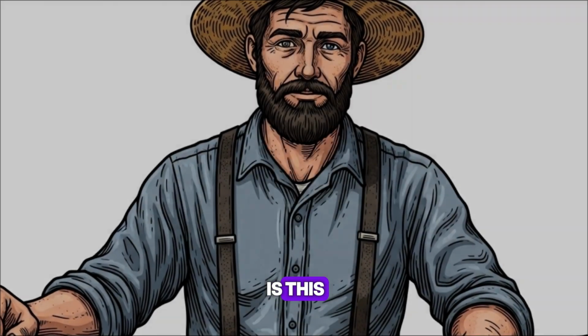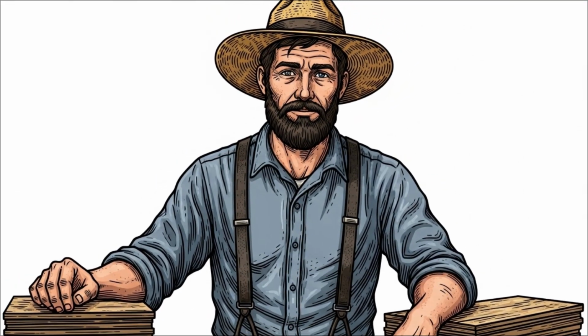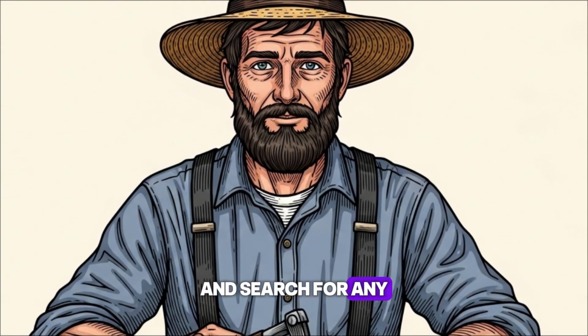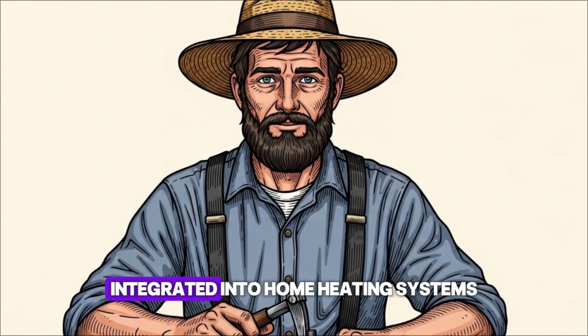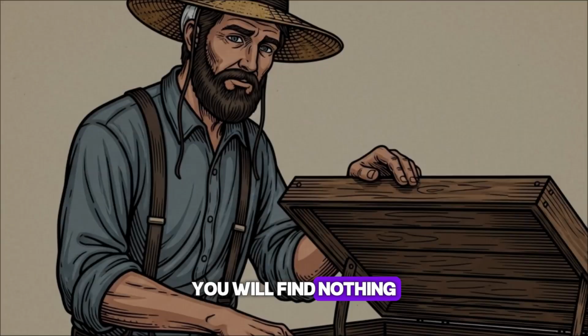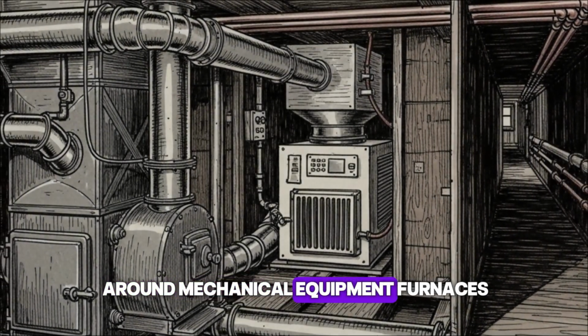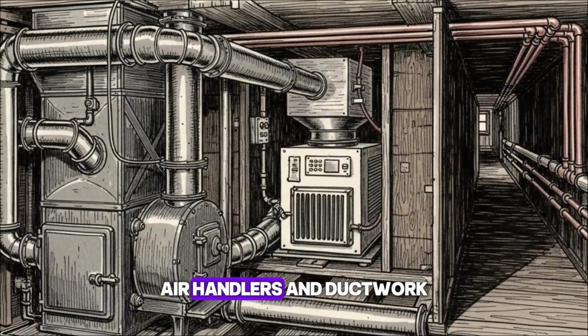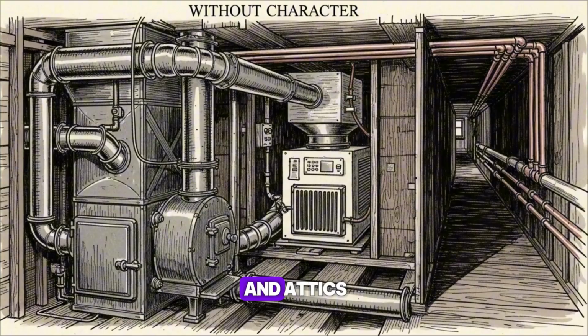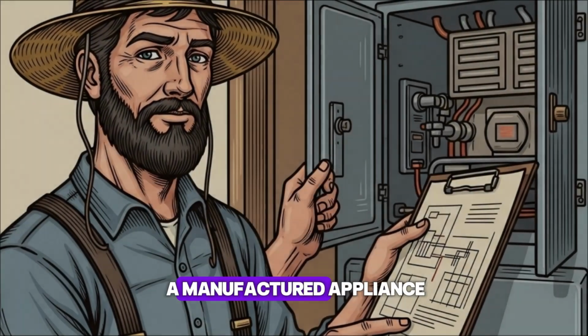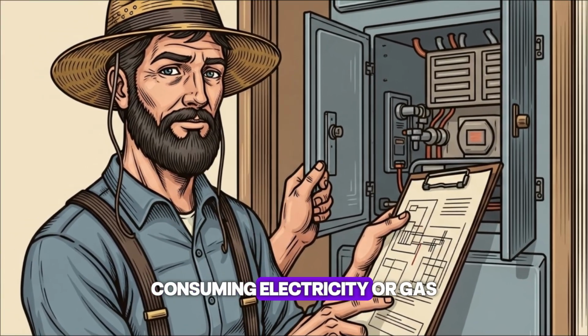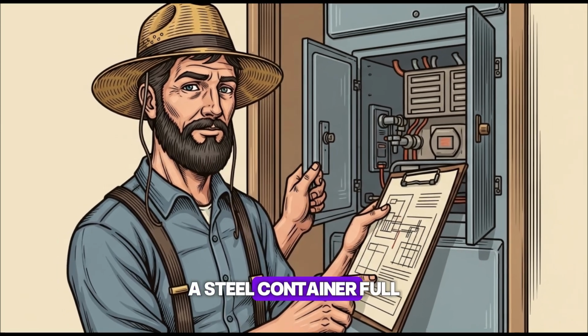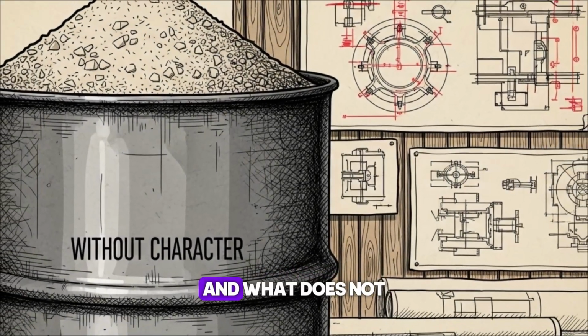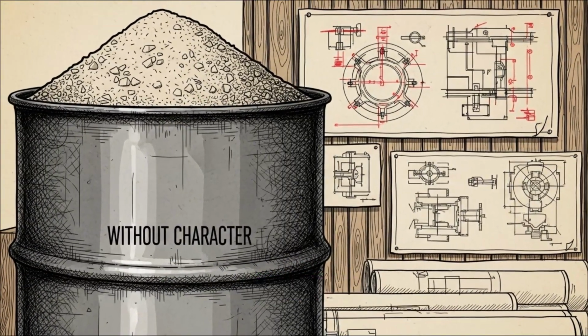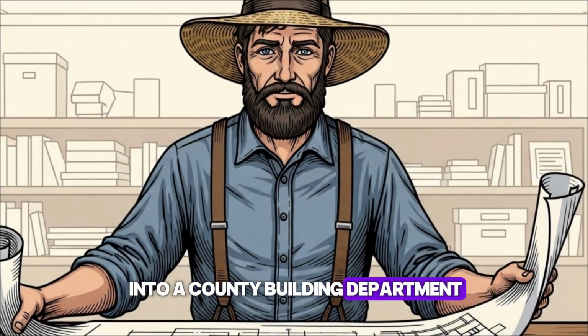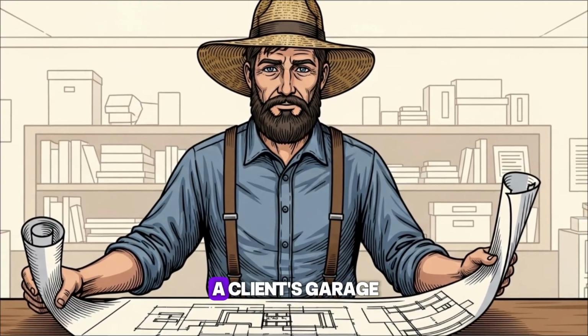So the obvious question is this: why does none of it exist in America? Open the International Residential Code and search for any provision allowing sand-based thermal storage integrated into home heating systems. You will find nothing. The code was written around mechanical equipment: furnaces, heat pumps, air handlers, and ductwork routed through crawl spaces and attics. Every compliance pathway assumes a manufactured appliance sitting in a utility closet consuming electricity or gas on demand. A steel container full of heated sand does not fit the template, and what does not fit the template cannot be approved. Picture a contractor walking into a county building department carrying blueprints that show a sand battery in a client's garage.